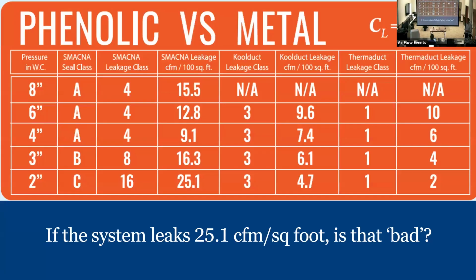Yep. All right, so this chart is a chart I made once upon a time to help me figure out how much leakage was okay. That formula up at the top has the class, the leakage per 100 square feet, and the pressure. Now notice the pressure is at an exponent that's less than 1. So what it tells us is, yes, pressure is important, but what's really important is how many holes are there in the duct. So we're derating the pressure to a certain extent. Most of our systems are tested at 4 inches for high pressure. There are some at 6 and some at 8, and almost none at 3. And everything that's low pressure is 2.